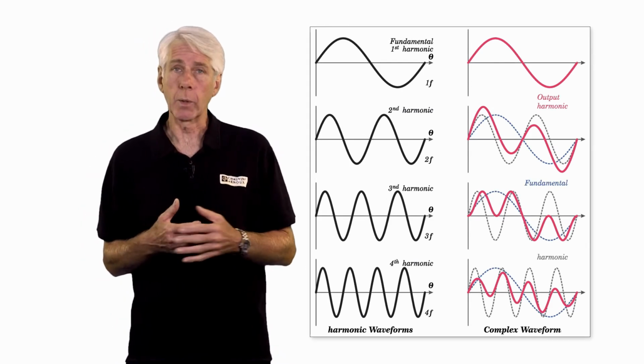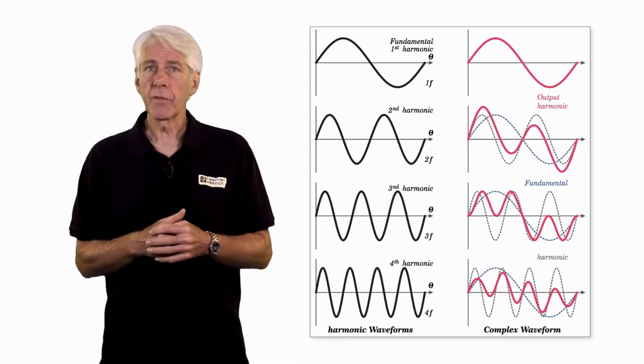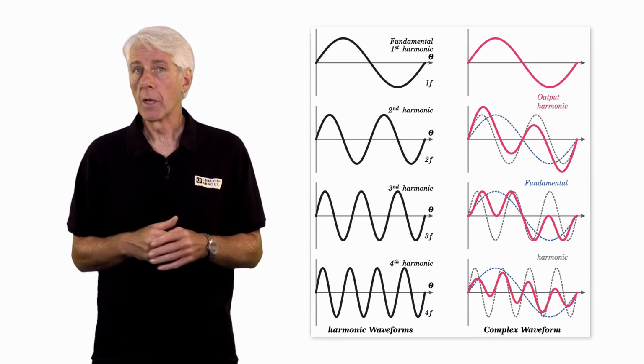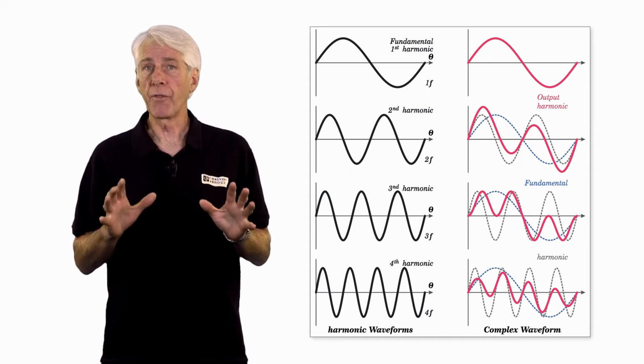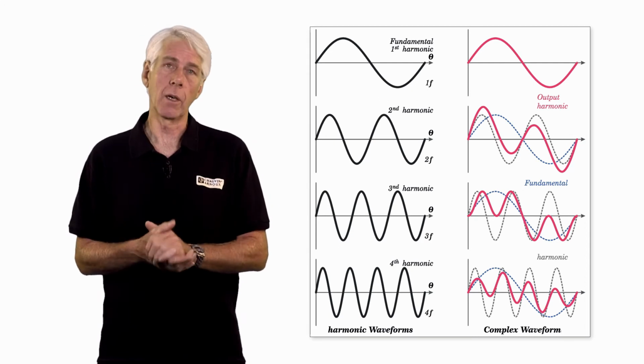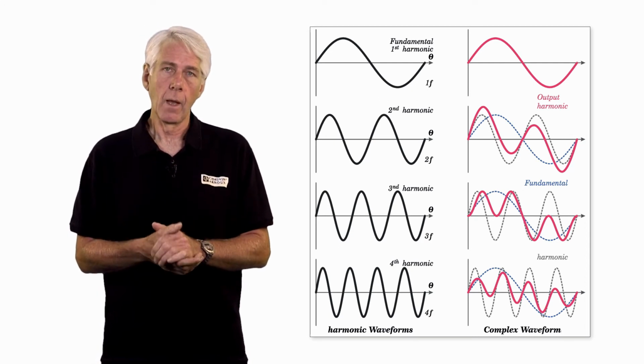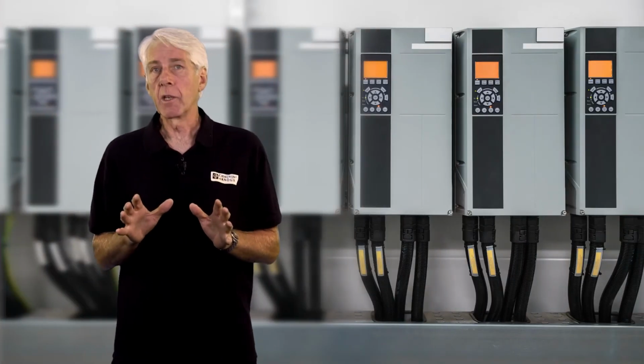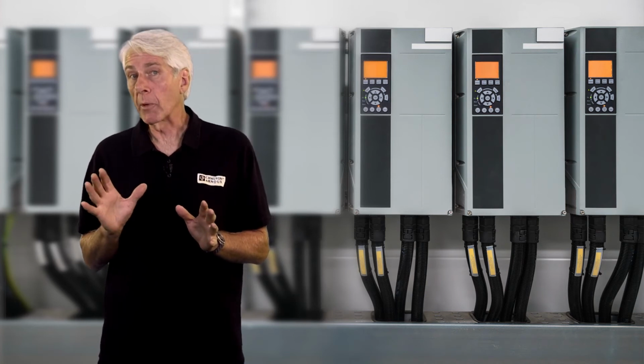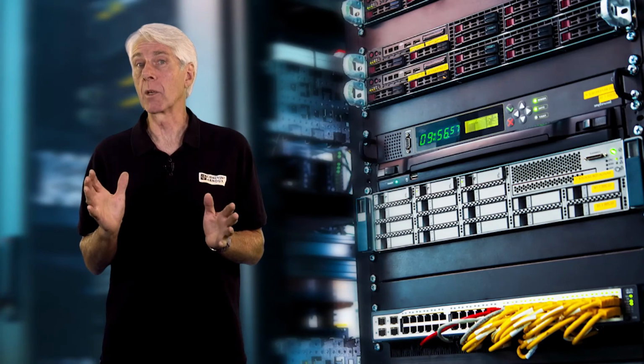Harmonics and other power quality issues are the subject of another one of our presentations. So here we'll just consider their effects on the electrical efficiency of an installation. Harmonic currents are generated by non-linear loads like variable speed motor drives, LED lighting, IT equipment, UPS systems, and solar PV inverters, to name just a few.